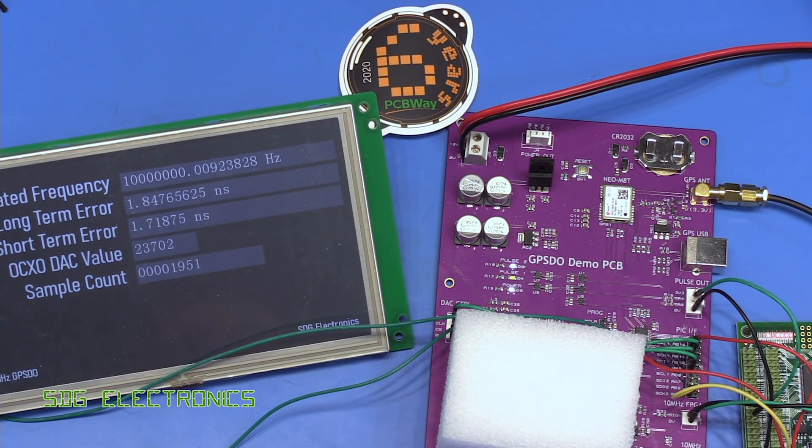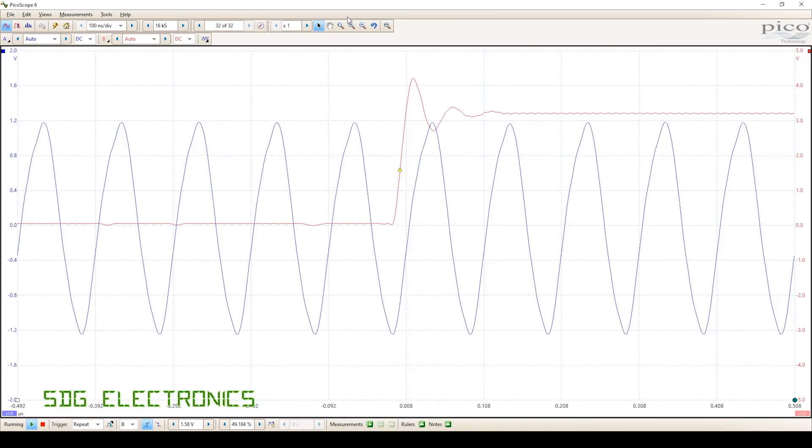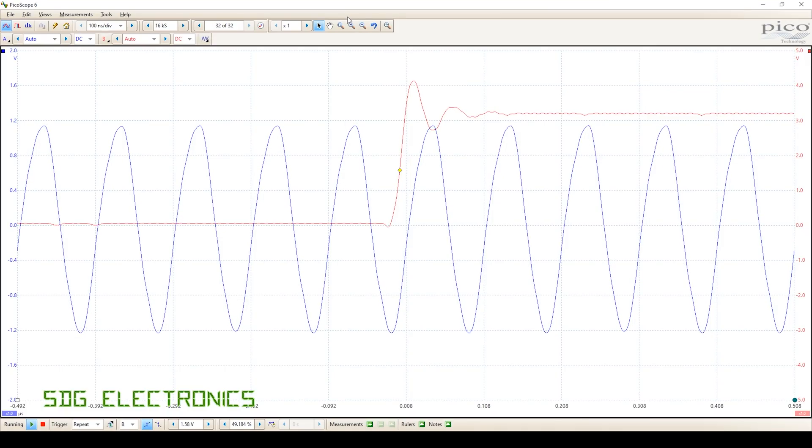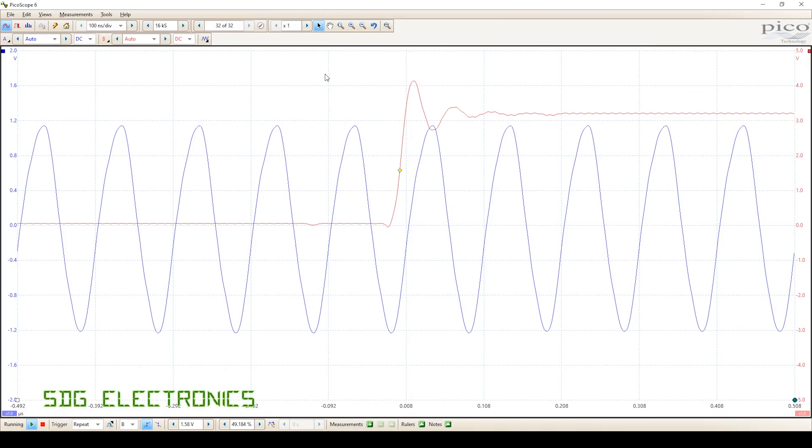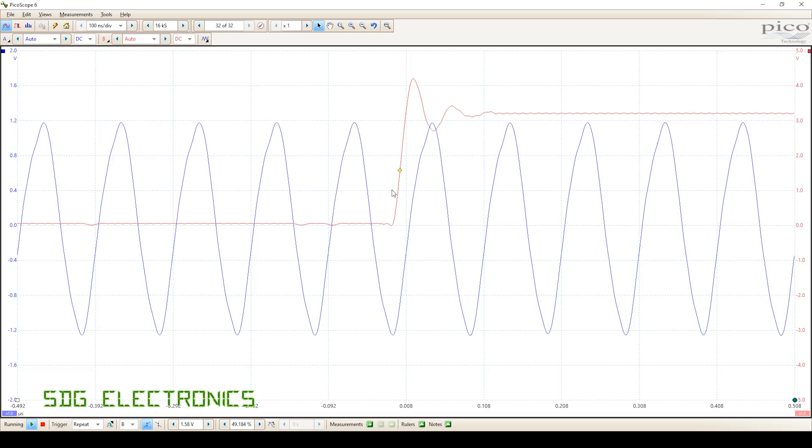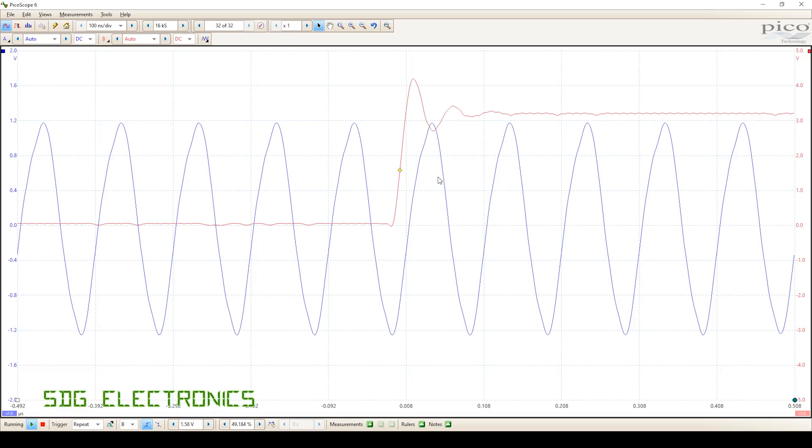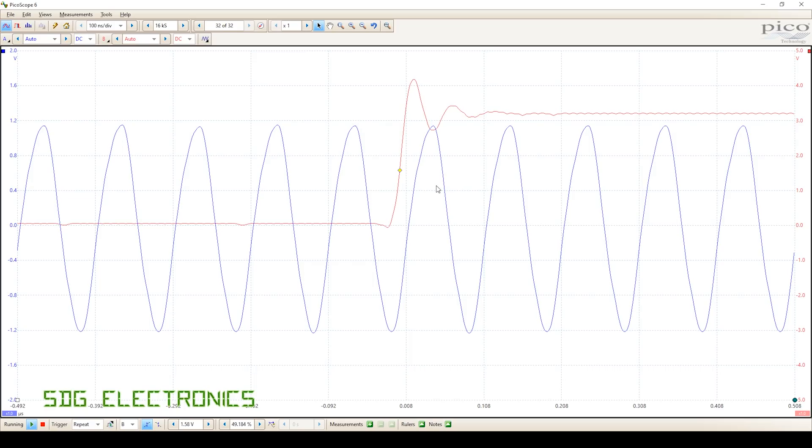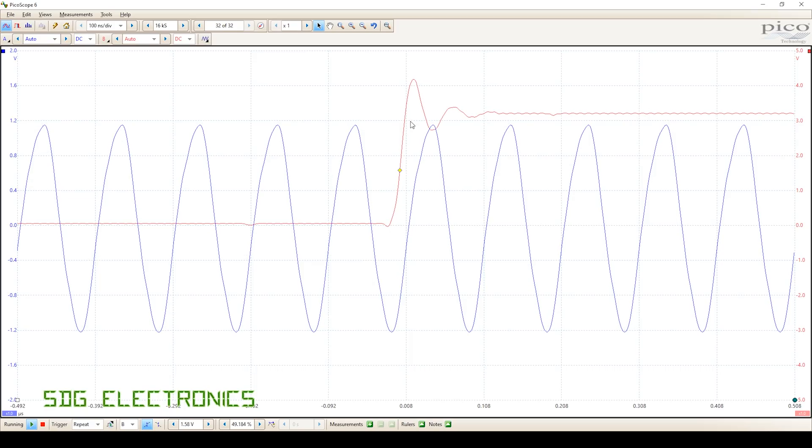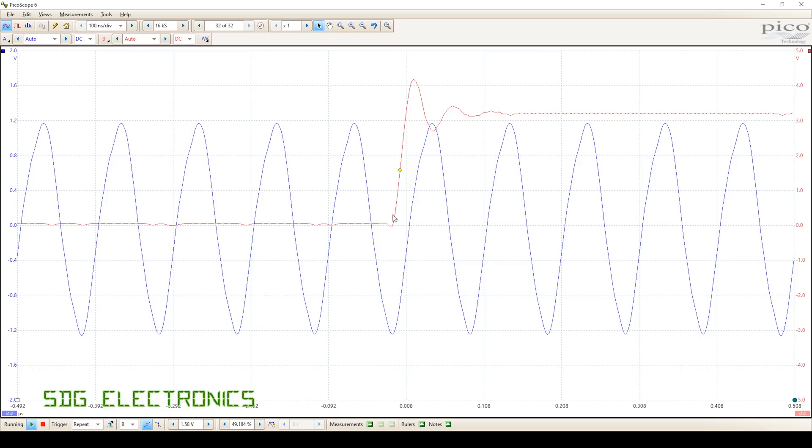One of the other things to consider with the frequency counter method is that the one pulse per second isn't necessarily synchronized with the 10 megahertz reference at all, other than by making sure that the frequency is correct. This one pulse per second that you can see in red on the scope happens to be rising from around the bottom of the sine wave here, but depending on when it locked on it could be anywhere along this sine wave without any particular preference.